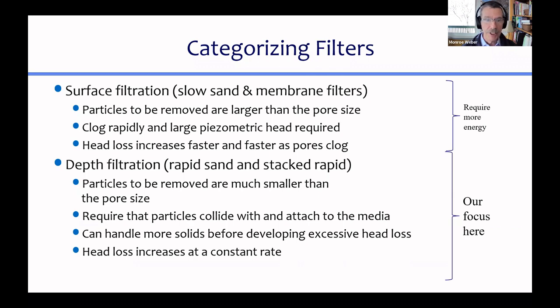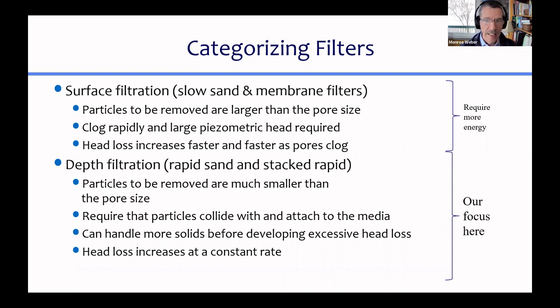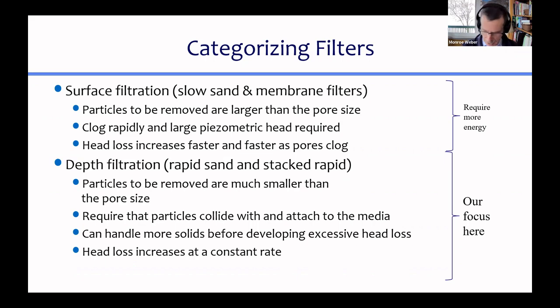The other filter that uses surface filtration — where particles are captured right when they're trying to enter the filter — is slow sand filters. Slow sand filters are the first kind of filters created. They have smaller sand media and much lower filtration rates, and they tend to capture almost all the particles right at the surface.